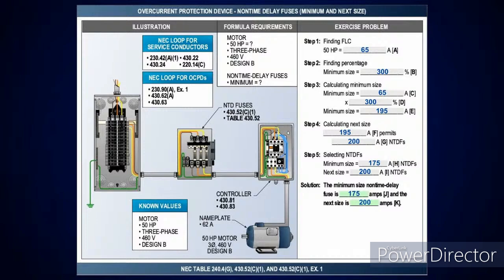And then if I look at step 4, and I actually go over and look at 430.52(C)(1)(a) and (b), it's going to tell you, in (a), I'm automatically permitted to go up to the next standard size if it didn't start on the inrush current, which would be a 200 amp. But if it'll start based on not exceeding the calculated value, I can drop down to the next standard size, which is 175 amp. So we got a minimum size at 175 and a next size at 200.